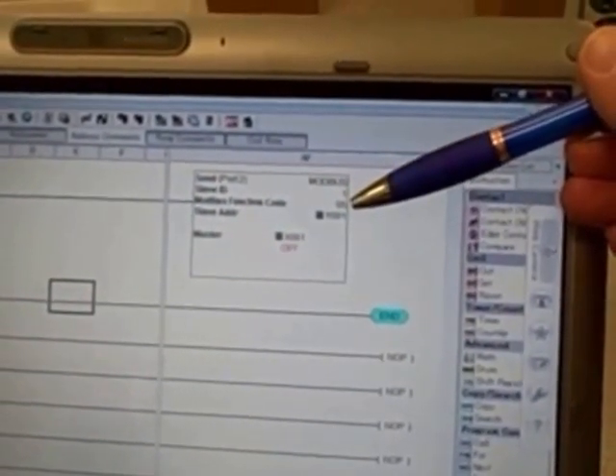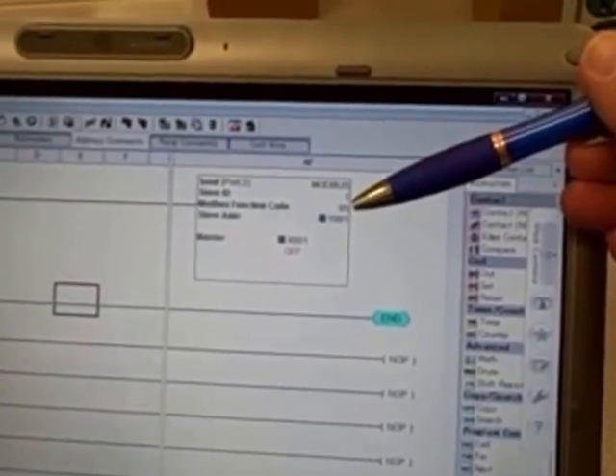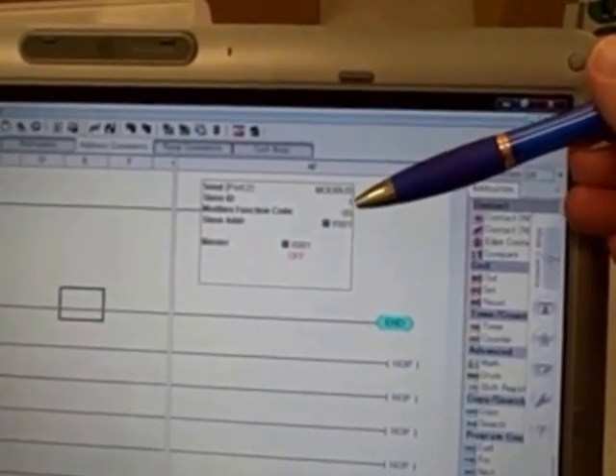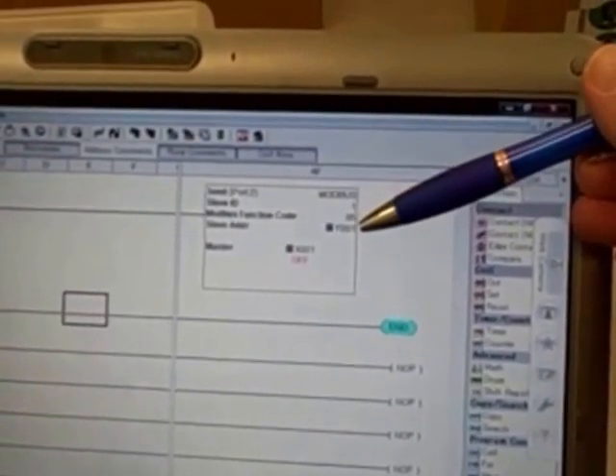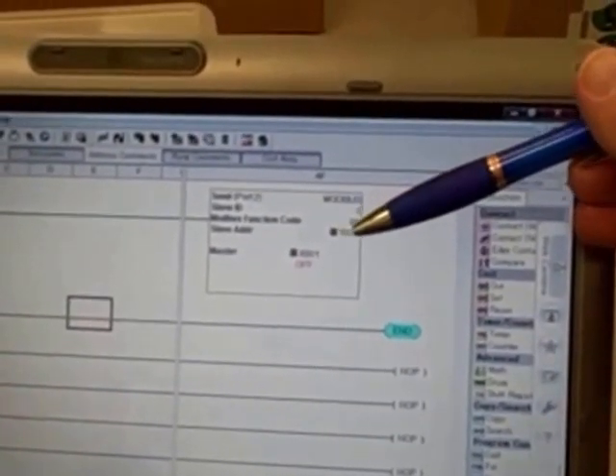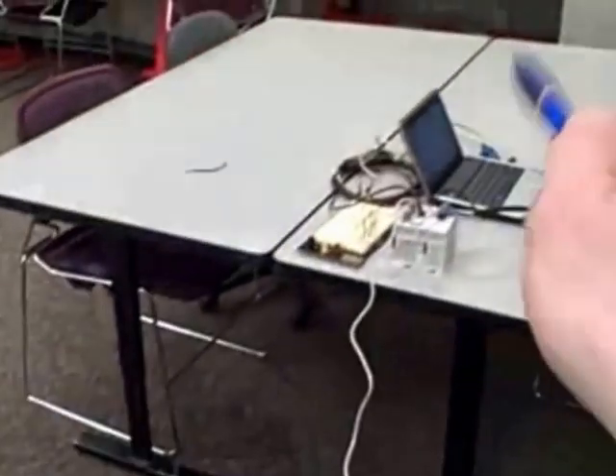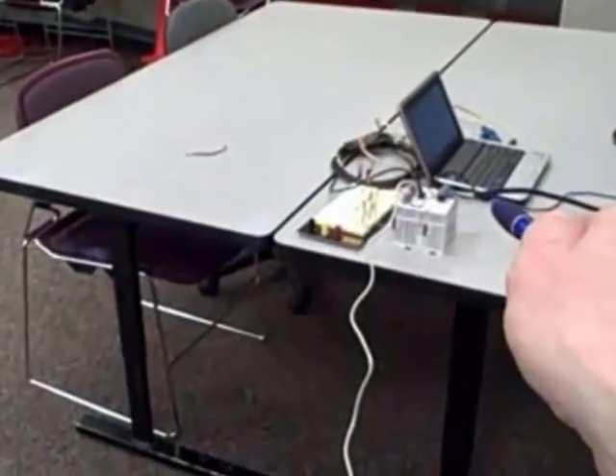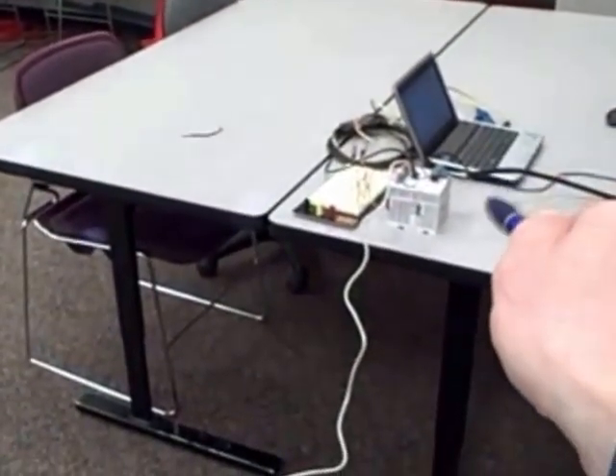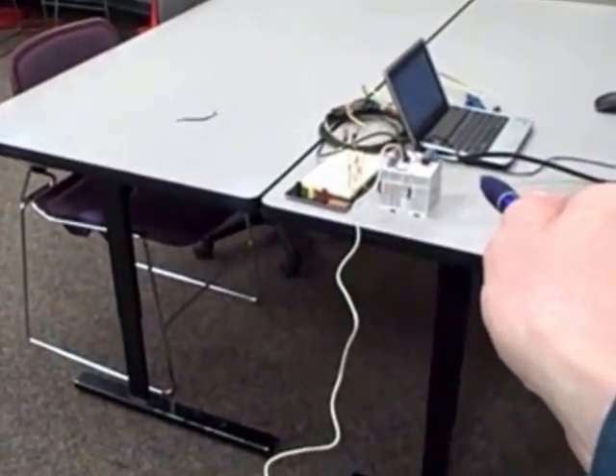According to this box it's going to use Modbus protocol and be talking to slave ID number 1. Modbus function code which is to write to a single coil. The slave address is coil Y1. That's going to be the first discrete output on the slave PLC. And we have set that up as slave address number 1.